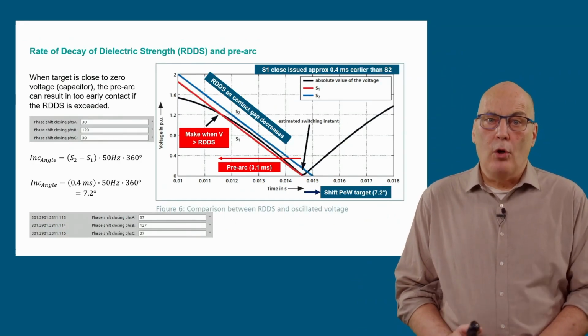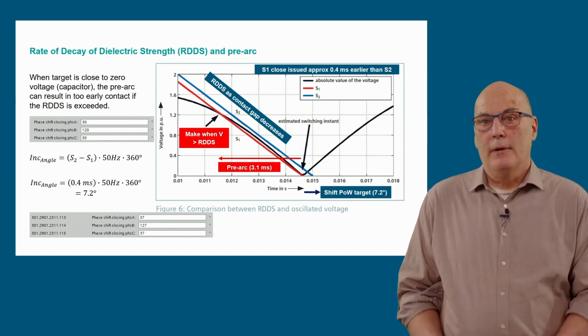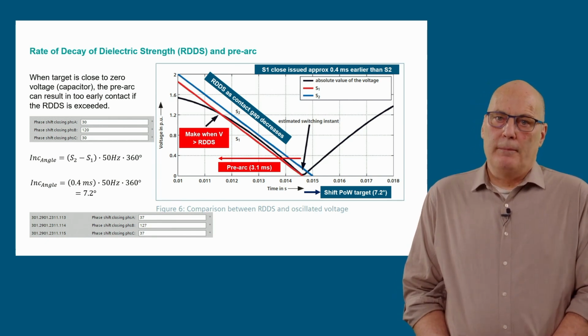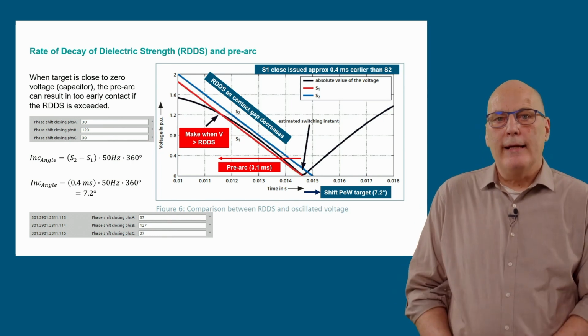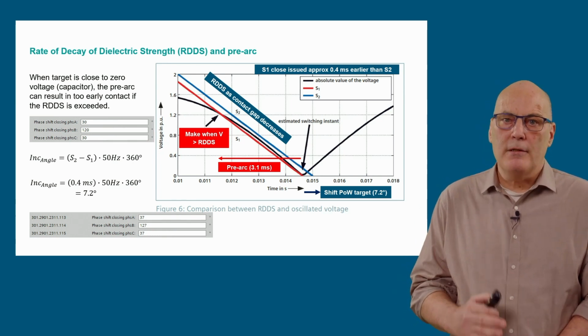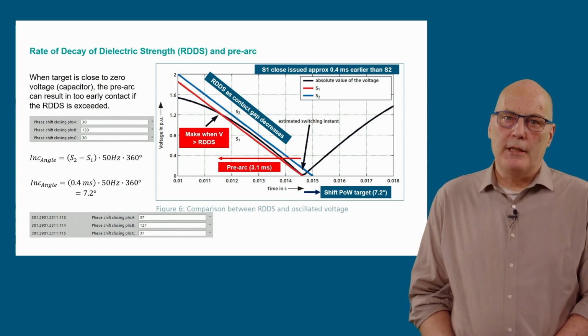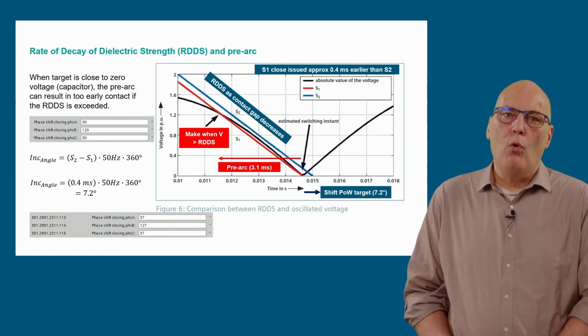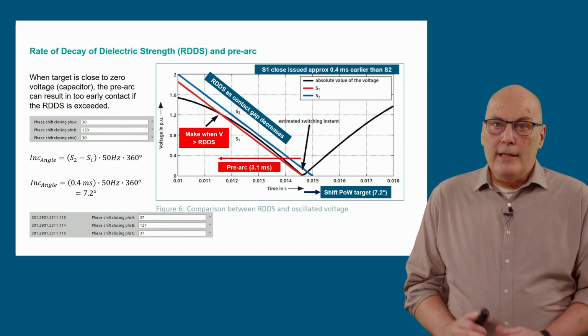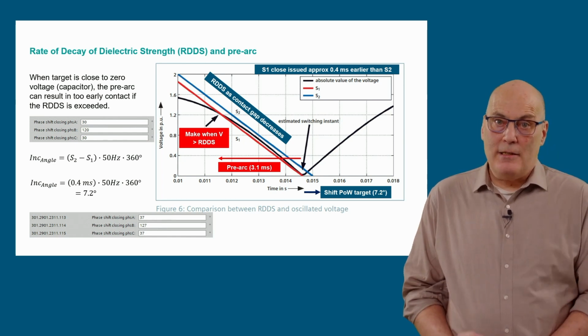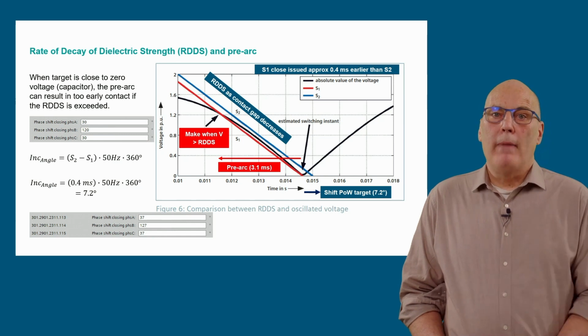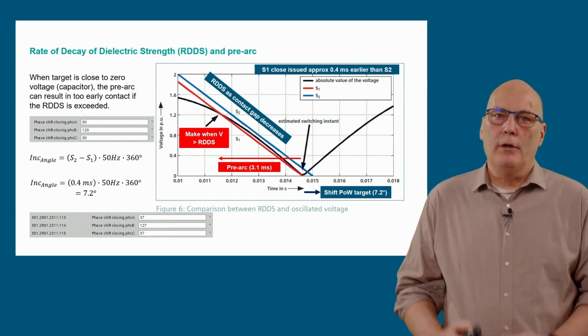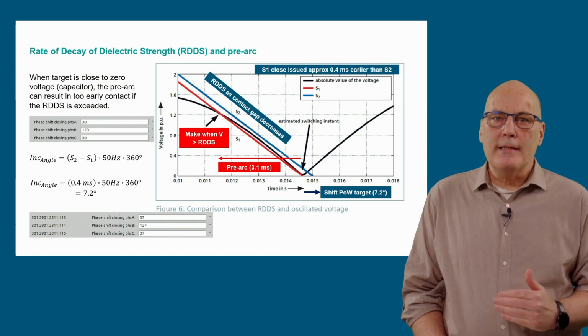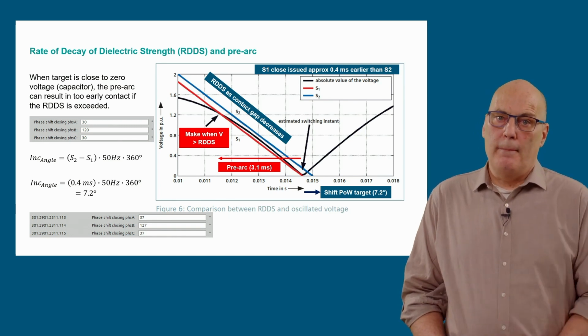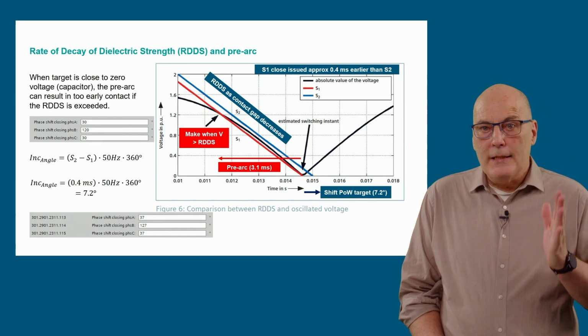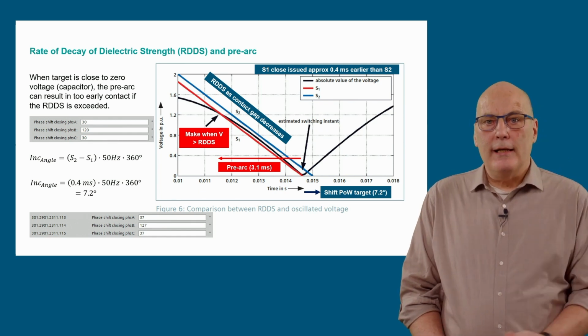The two switching times are only a short distance apart, less than half a millisecond, as can be seen where they intersect the x-axis at 15 milliseconds, respectively 14.6 milliseconds, so 0.4 milliseconds apart. At this point, where they intersect the x-axis, the breaker primary contacts make first mechanical contact, as shown from earlier. This is the end point of the closing time.